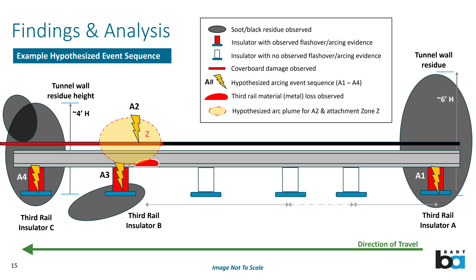So the hypothesis under evaluation is that insulator B did not fail on its own - it was an initiating event from above, a DC arcing event. We'll look at some actual photos from this incident. Once A failed, then B would have failed in quick succession, as well as C. We're still evaluating A to determine if that initiating source was at play at that location too.